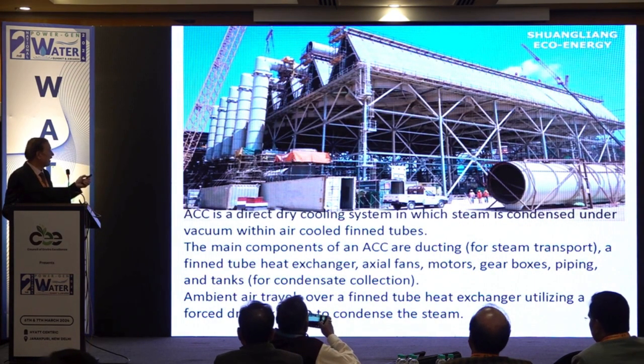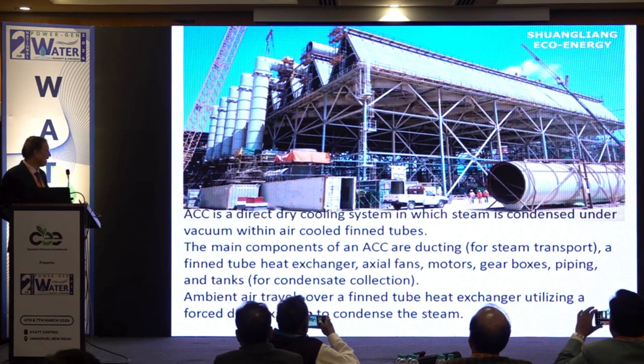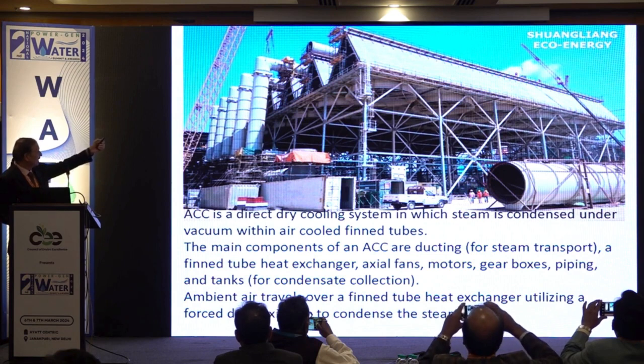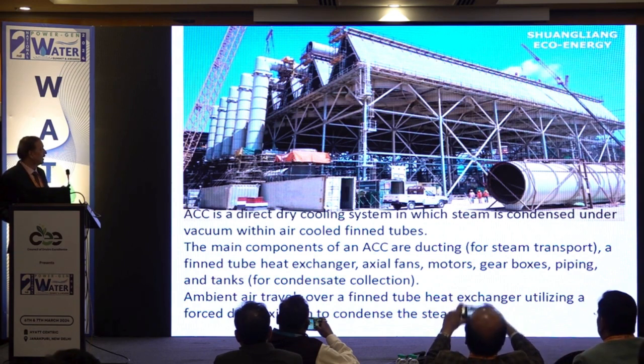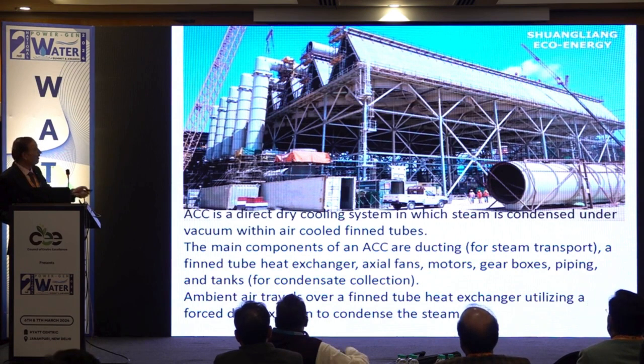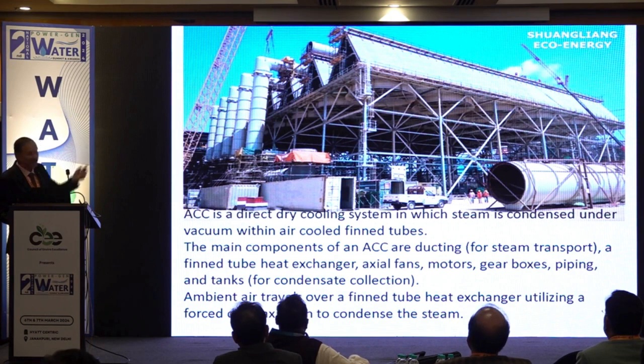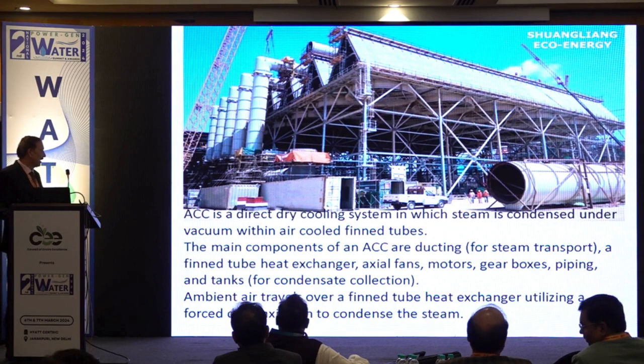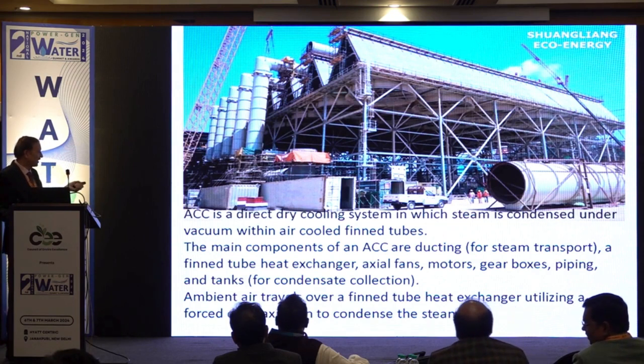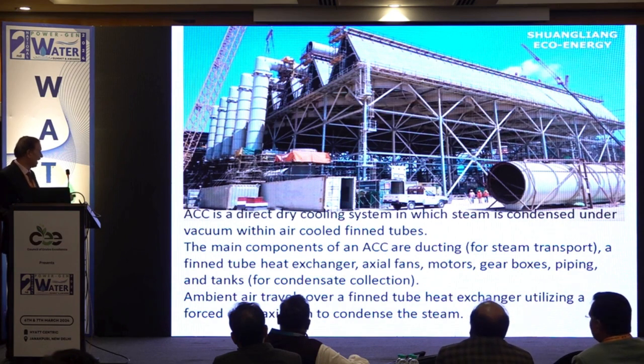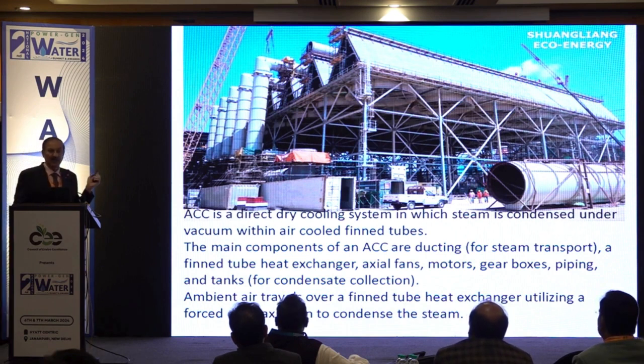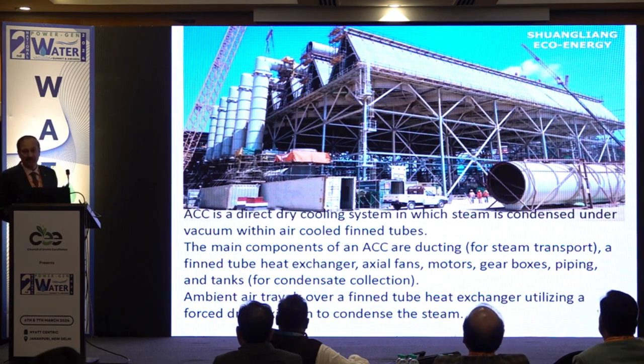This is the picture of the direct dry cooling system in which steam is condensed under vacuum within air-cooled fin tubes. You can see this is the picture of the air-cooled condenser. So there are fans below the air-cooled condenser which is sucking the air, and the steam is coming in the air-cooled condenser, ultimately getting condensed. The main components of ACC are ducting, fin tube heat exchanger, axial fans, motors, gearboxes, piping and tanks. Ambient air travels over a fin tube heat exchanger. Again, to increase the heat exchange area, we have a fin tube heat exchanger utilizing a forced-draft axial fan to condense the steam.